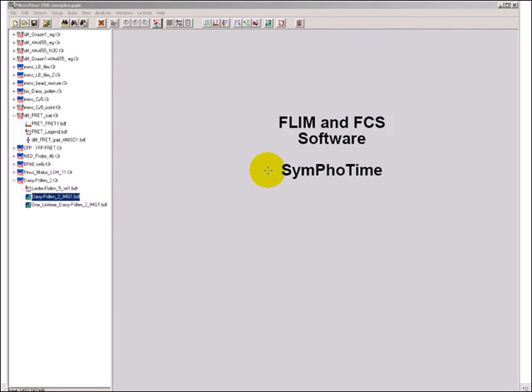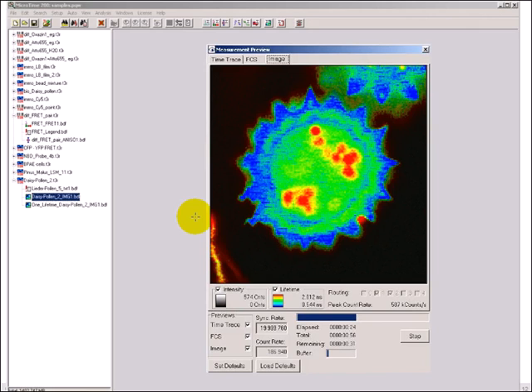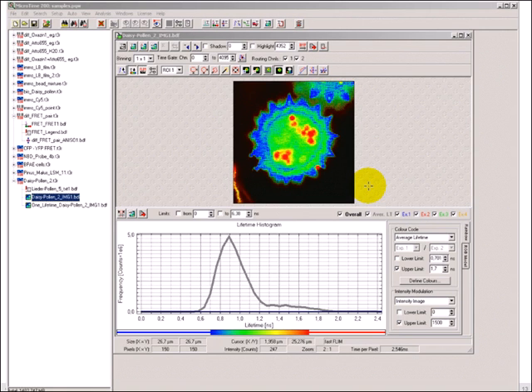The SymPhoTime software contains all steps from FLIM and FCS data acquisition to analysis. On the left side, all measurements and their different analysis procedures are displayed in a tree view. In order to start a FLIM measurement, just press the RECORD button and then start the scanning. The fast FLIM image is displayed during image acquisition. To check the FLIM quality, the number of photons and the count rate of the brightest pixel are displayed. If enough photons are acquired, recording is stopped using the STOP button. The fast FLIM image and the lifetime distribution are then displayed, and lifetime fitting can be performed either at selected regions or pixel per pixel.